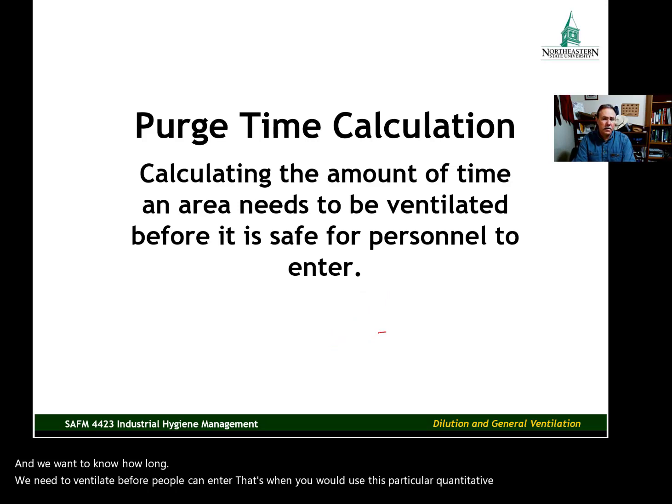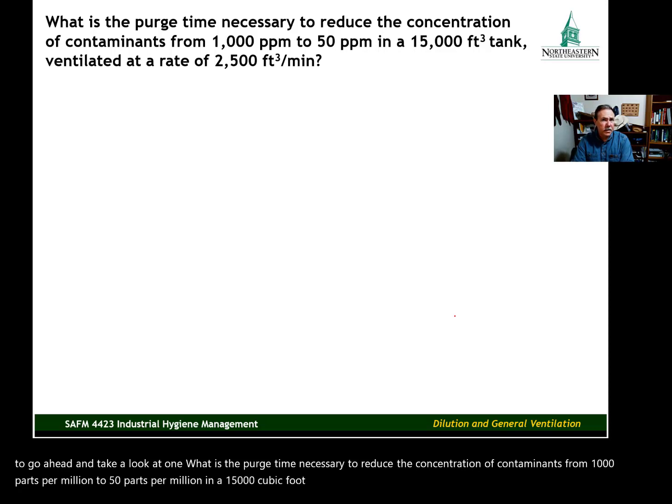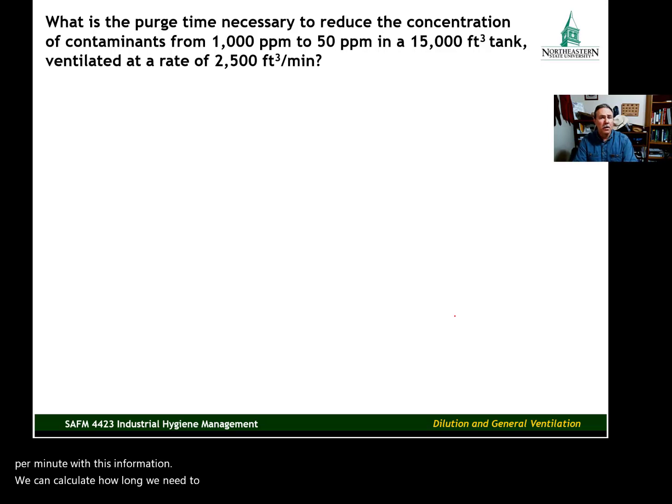Here's a problem to take a look at. What is the purge time necessary to reduce the concentration of contaminants from 1,000 parts per million to 50 parts per million in a 15,000 cubic foot tank, and the tank is being ventilated at a rate of 2,500 cubic feet per minute? With this information we can calculate how long we need to ventilate before people can enter, before it gets down to that 50 parts per million desired concentration.